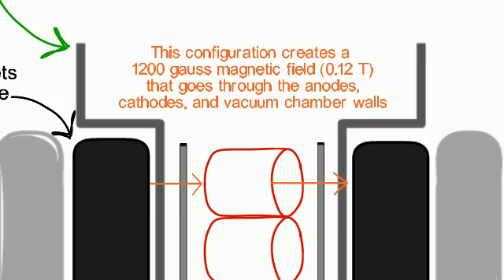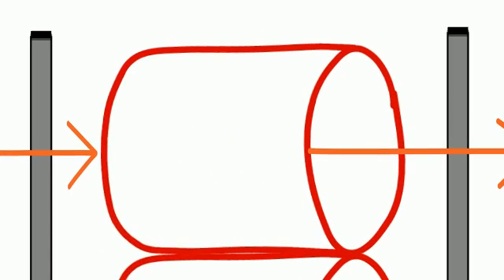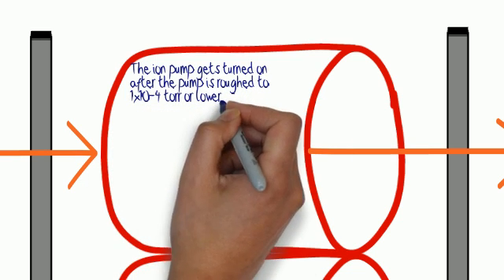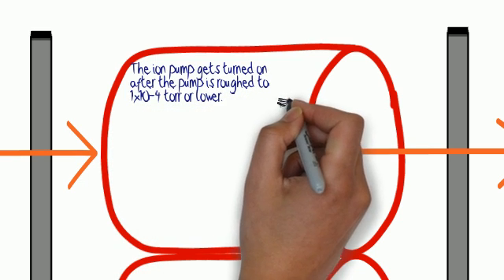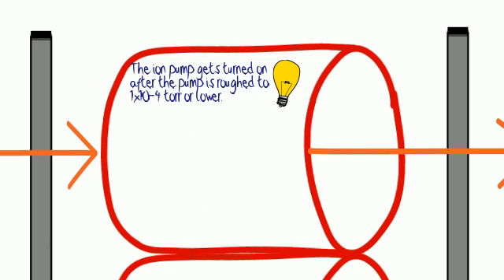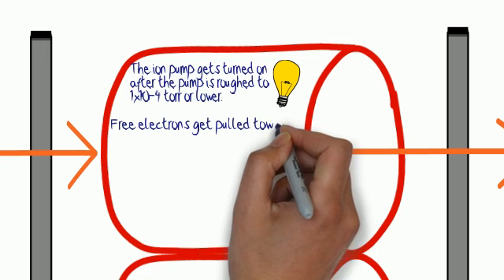There it is. Zooming up on that, we're going to actually rough this pump down to 10 to the minus 4 torr or lower if we can, and go ahead and turn it on. 7,000 volts is what we typically use, but the ion pump will operate anywhere between 3 and 7,000.